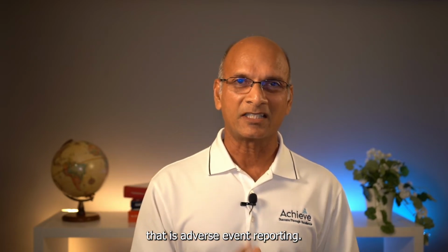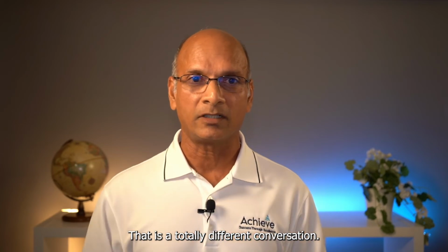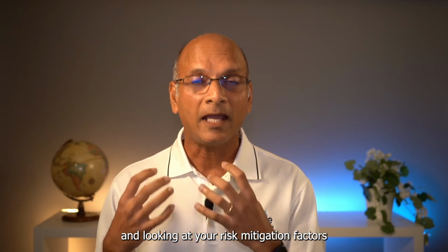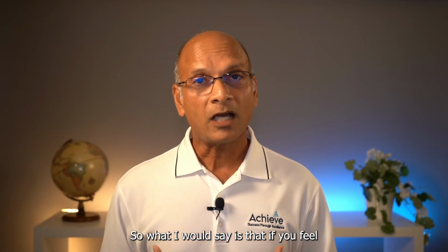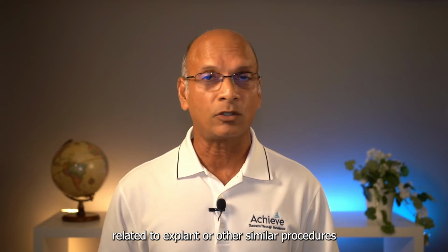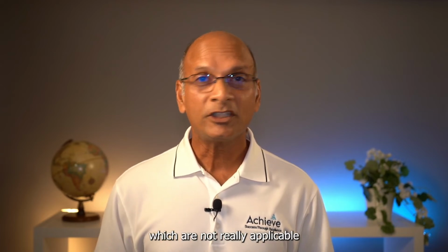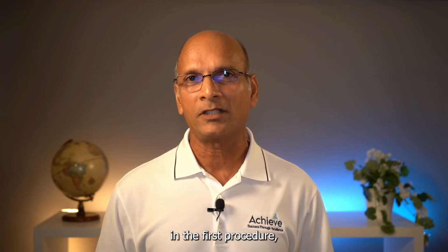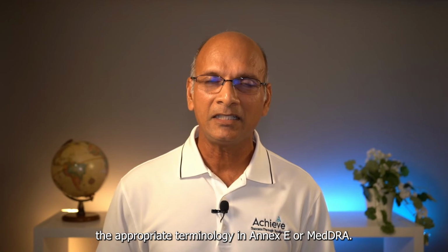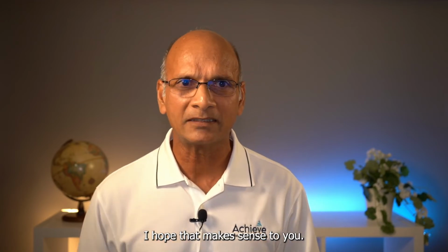So for risk, now we are not talking about case by case decisions. That is adverse event reporting. That is a totally different conversation. We are talking about how to treat this scenario for risk analysis and looking at your risk mitigation factors or control factors. So what I would say is that if you feel that there are some certain outcomes specifically related to explant or other similar procedures which are not really applicable in the first procedure, then look up the appropriate terminology in Annex E or MedDRA. I hope that makes sense to you.